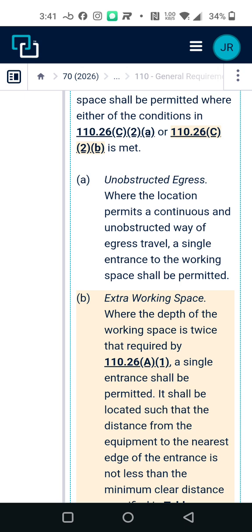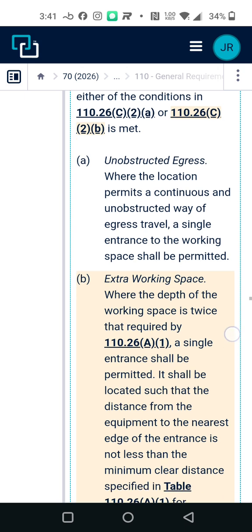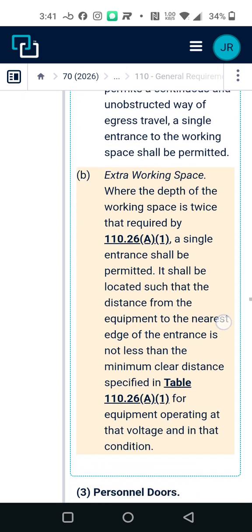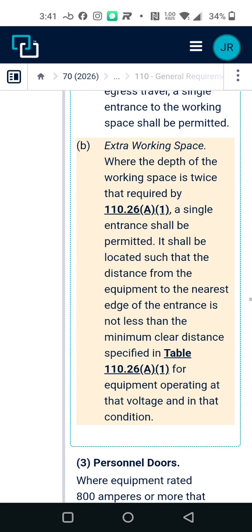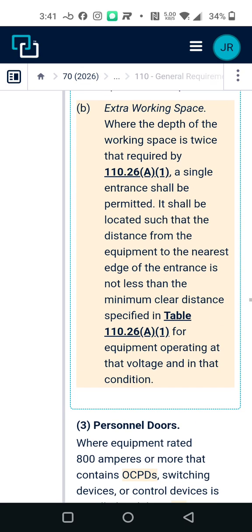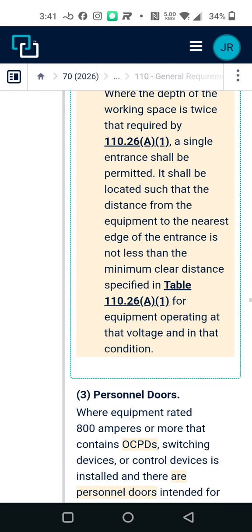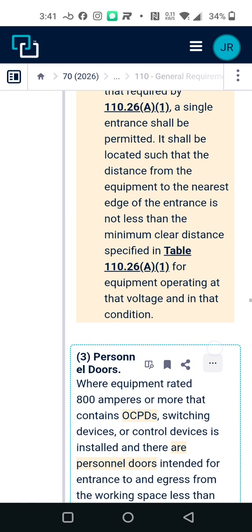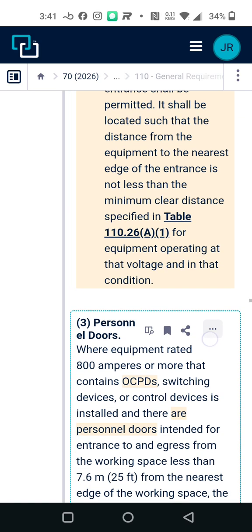Unobstructed egress, where the location permits a continuous and unobstructed way of egress travel. Extra working space, where the depth of the working space is twice that required by 110.26. A single entrance should be permitted. It should be located such that the distance from the equipment to the nearest edge of the entrance is not less than the minimum clear distance specified.